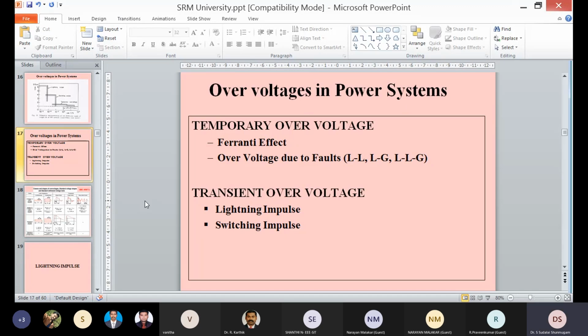So again, I am redefining that. When the system voltage is less than 220 kV, you have to remember this, we call that a high voltage line. And when it comes to a high voltage line, the key important parameters are power frequency withstand voltage and lightning impulse voltage. Switching impulse voltage doesn't come into the picture yet. It will happen, of course, the circuit breaker is going to clear that, but the insulation of the system is quite enough to withstand switching impulse voltage. However, the significance of switching impulse voltage will be quite higher when the system voltage is more than 245 kV.